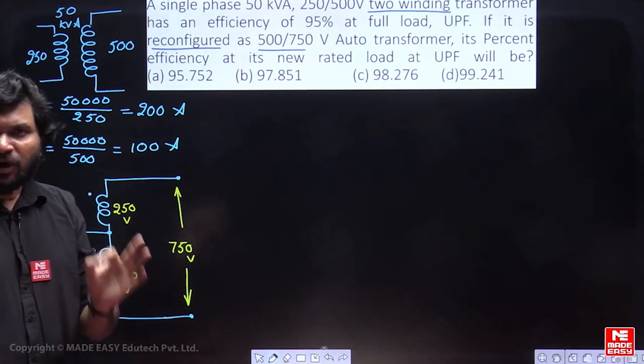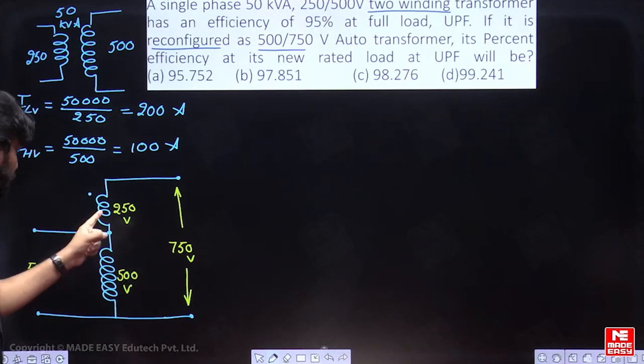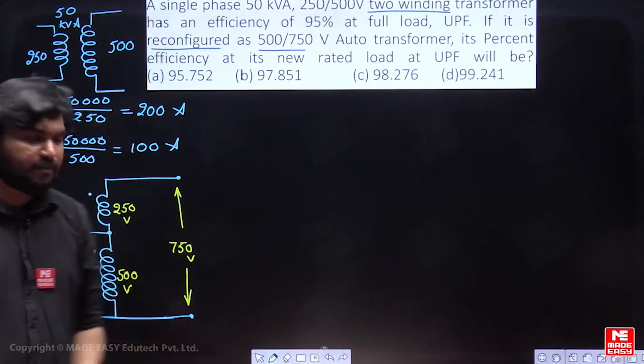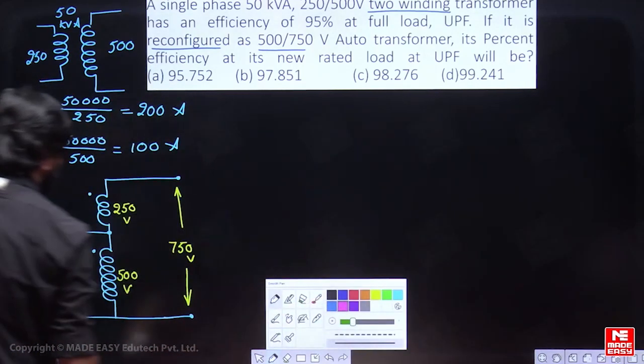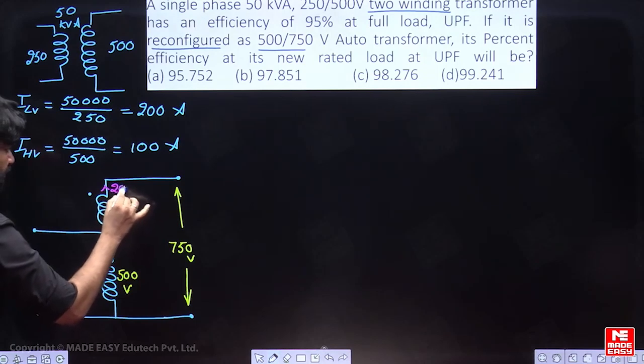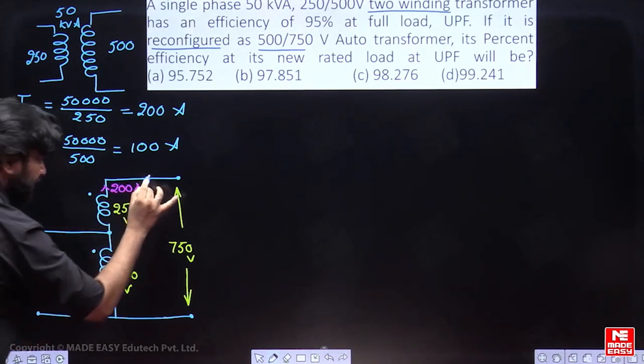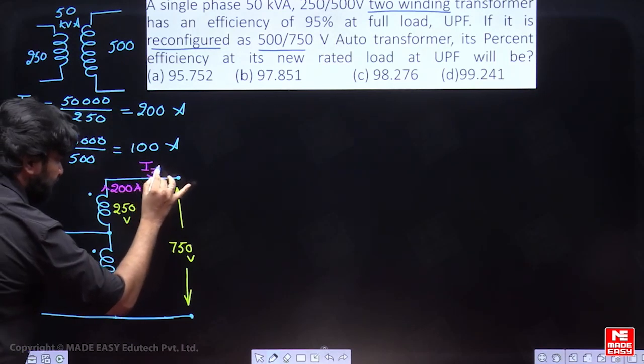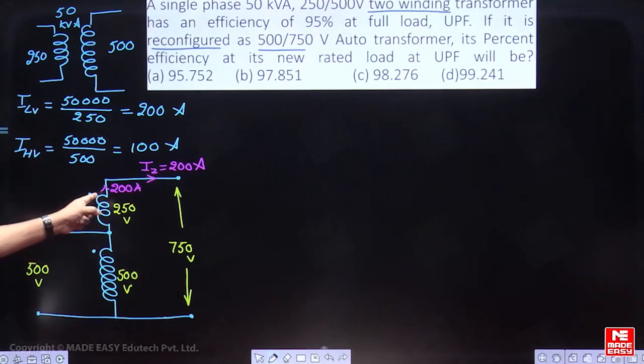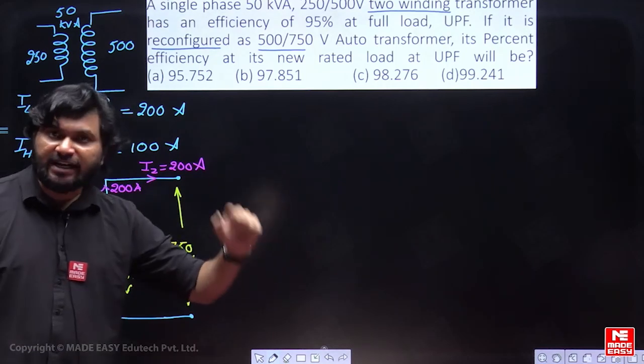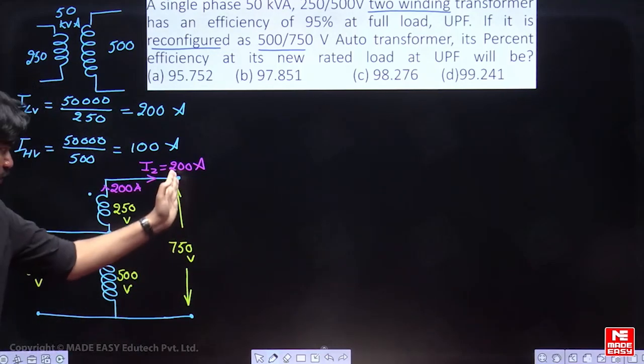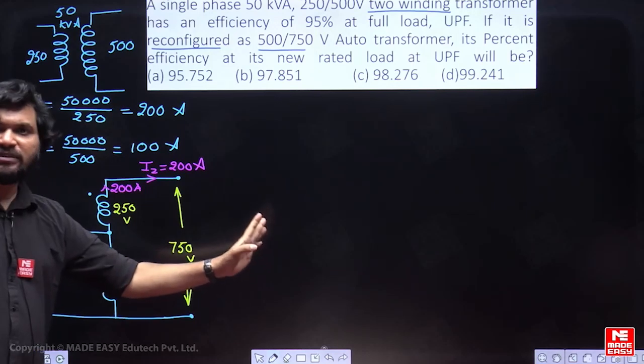First, fix the current rating of the 250-volt winding — start with that point. The current rating of this winding is 200 ampere. So obviously, I2 is 200 ampere. The current flowing in this winding must be 200 ampere only, because the rating of that particular winding is 200 ampere. So if you connect a load, that load must carry 200 ampere only.